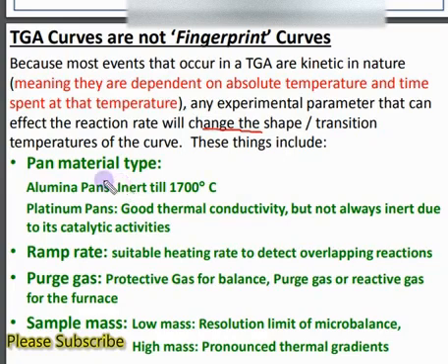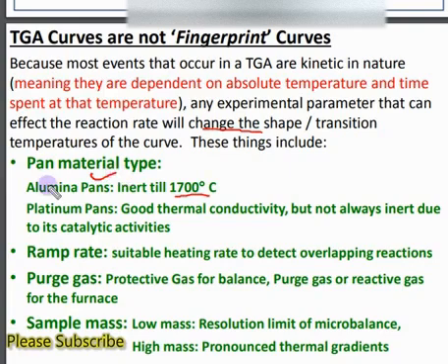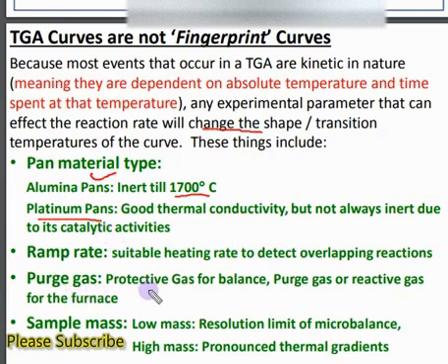The first parameter is the material type — the pan. Alumina pans are inert up to 1700°C. Platinum pans are thermally good conductors, but they are not as inert as alumina and can show catalytic behavior. Similarly, the ramp rate also influences the TGA curves — a suitable heating rate is needed to detect overlapping reactions. Purge gas or reactive gas also influences the balance and sample.